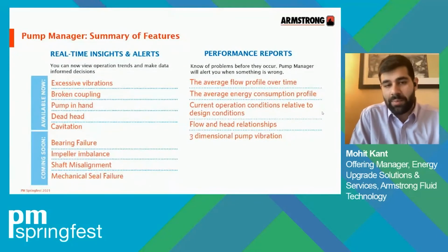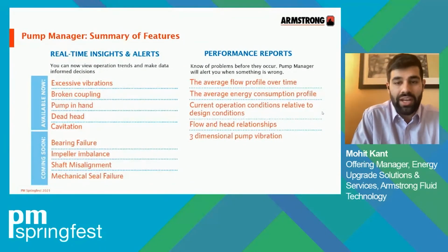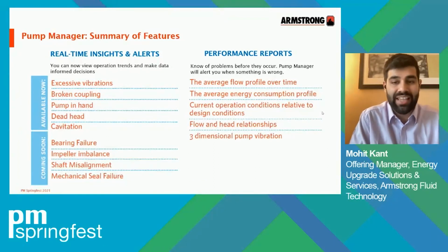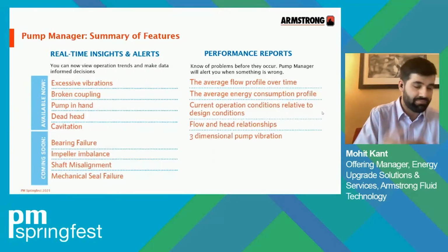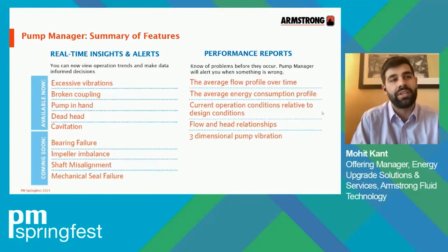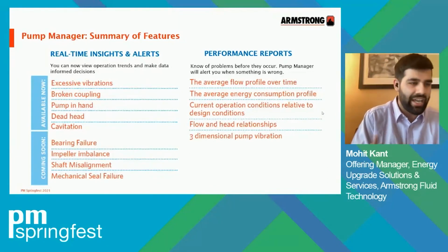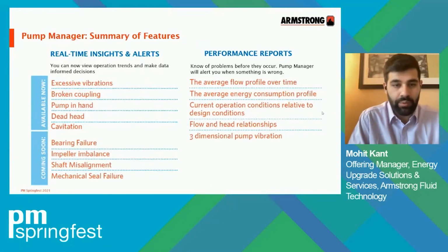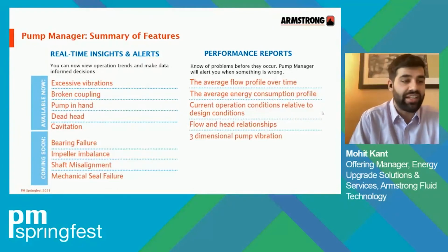Today, powered by IBM Watson's Cloud Analytics engine, we're able to detect pump behaviors like deadhead, excessive vibration, and cavitation, which are incidentally some of the most common issues you see with pumps in the field. Shortly, we will be adding advanced features such as detecting the onset of mechanical seal and bearing failures. Additionally, monthly performance reports are generated in the cloud and shared with end users through an automated email service.